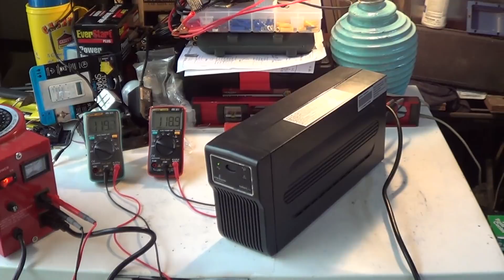And anytime the power goes wrong, they have no choice but to go to their battery. You move up a little in the APC product matrix, and you'll find that they have automatic voltage regulation capability, but it's only in the boosting direction. That is to say, when the line voltage goes low, they can bring it up, but if the line voltage goes high, they have to switch over to their battery.